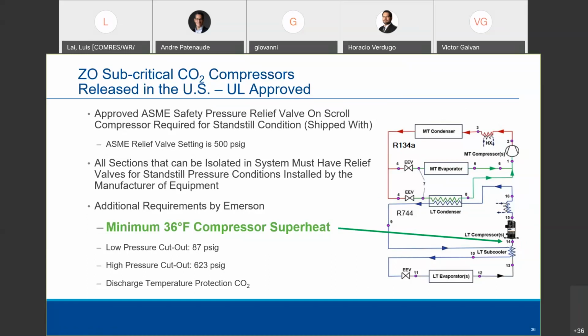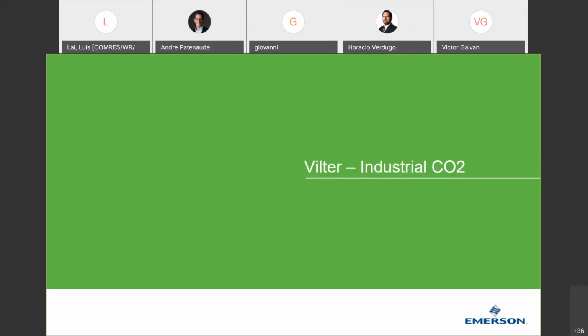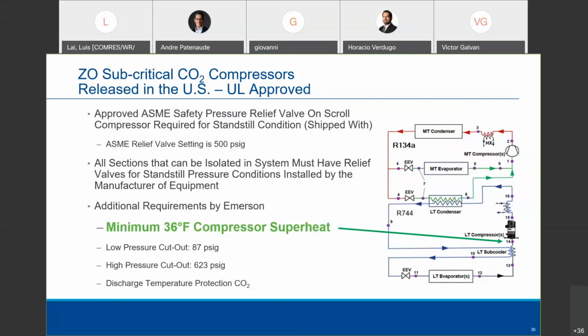your refrigerant gets soluble in the oil. So you actually lose oil viscosity if your superheat is low. You got to keep your superheat high to make sure that your oil is in good shape to lubricate all the bearings and thrust surfaces. And there is a chart available. It's a really cool chart. It's a graph that actually shows the drop in viscosity with drop in superheat. So it's important to note that. And you read our literature, you read Dorin's literature, you read Bitzer's literature, they all read the same thing. When you do the conversion from Celsius to Fahrenheit, it's 36 degrees for low temp CO2.